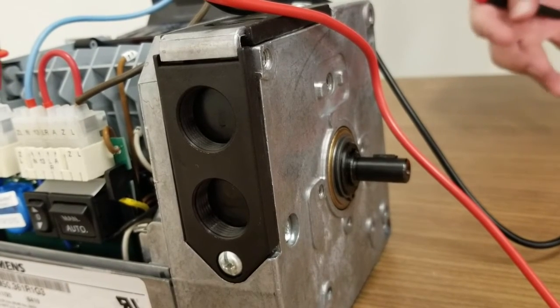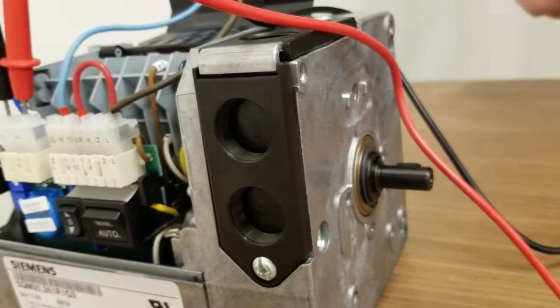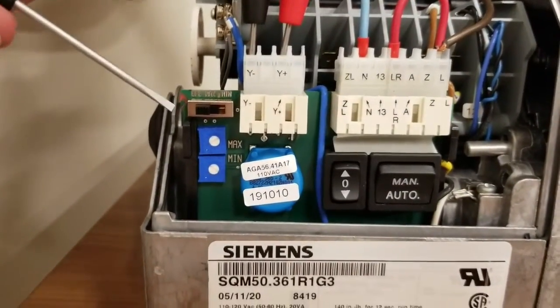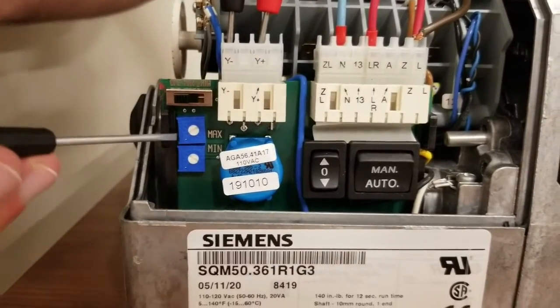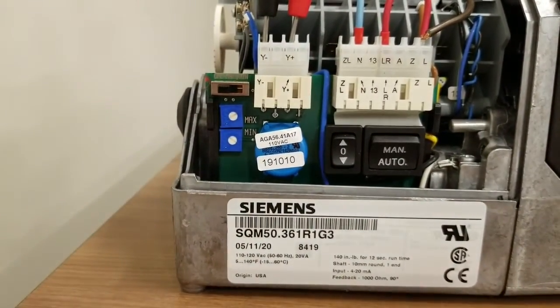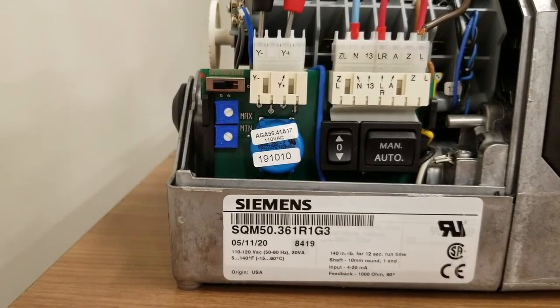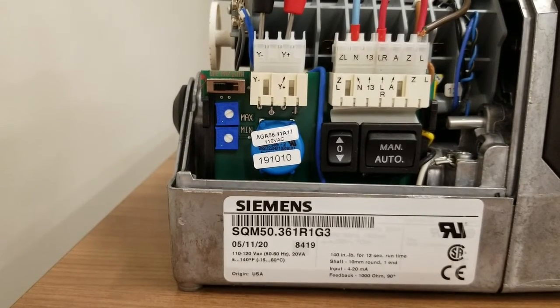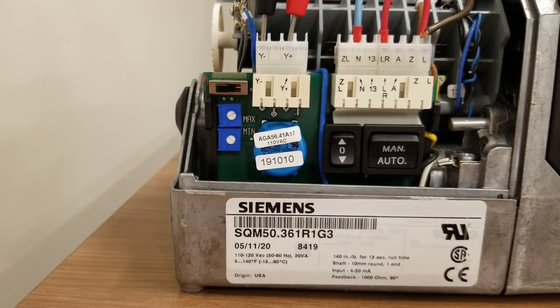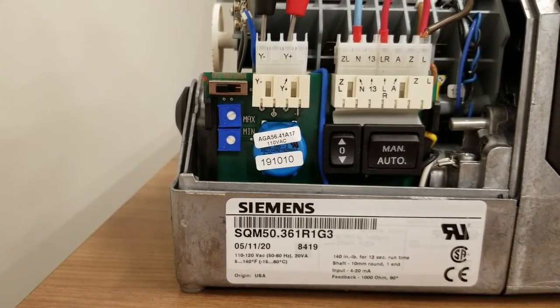Once we've reached our maximum open position, we want to make sure that we have a properly scaled input. The way we do this is to use a small flathead screwdriver like this one and adjust the max pot, this blue max pot. You're going to rotate that in a counterclockwise direction until the motor starts to drive slightly downward. This adjustment will ensure that we are utilizing the full range of the input signal.